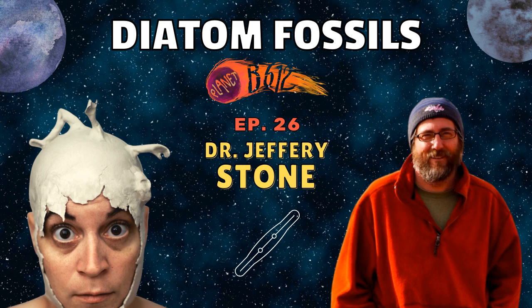The scanning electron microscope scans an electron beam over a little area on a specimen, and the electrons interact with whatever that specimen might be. Most of the electrons actually penetrate and knock an electron out from the material, so it's degrading the material one electron at a time. Those electrons are then captured by a detector that has a positive charge. Electrons are immediately pulled towards things with a positive charge because they have a negative charge.